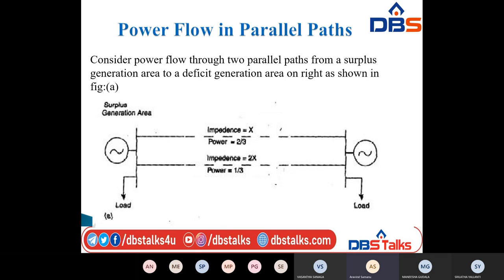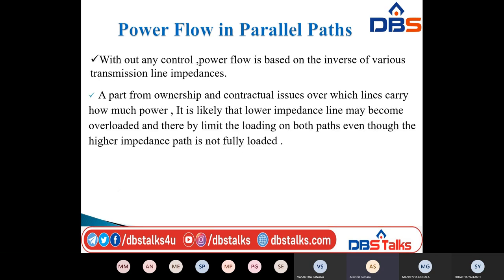Consider power flow through two parallel paths. One side is the surplus generation area and the other is the deficit area. Without any control, the power flow is based on the inverse of various transmission line impedances. Apart from ownership and contractual issues over which lines carry how much power, it is likely that the lower impedance line may become overloaded.